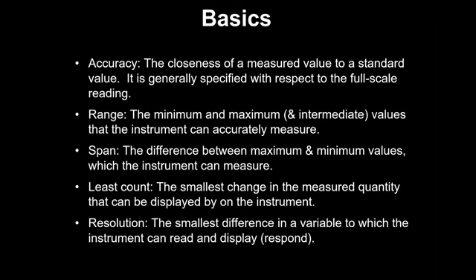The next is resolution. When we are doing a measurement, there are two parts. One part is the sensor, which is basically the probe, and another is the display unit. Resolution is the characteristic of the sensor, whereas the least count is the characteristic of the display. Resolution is the smallest difference in the variable. When we are measuring temperature, the variable is temperature. So if the temperature goes from 4 to 4.1, and our sensor can pick it up, that means it has a resolution of 0.1 degree.